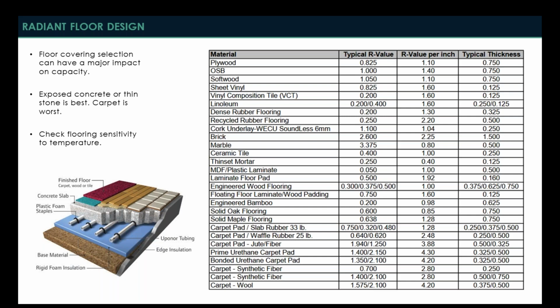It's also very, very important to find out what the sensitivity is, and this is maybe most true for wood flooring applications, because some wood floors can be very sensitive to not only minimum and maximum temperatures, but the range between those two. So oftentimes when we have applications for radiant floors that want to have a wood surface, bamboo comes to mind, because bamboo is a very structurally consistent wood that does not expand and contract as much.